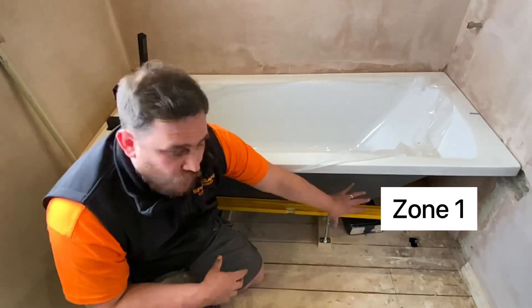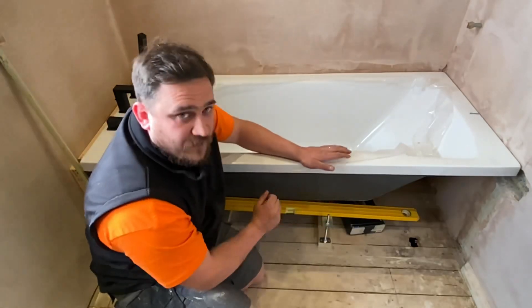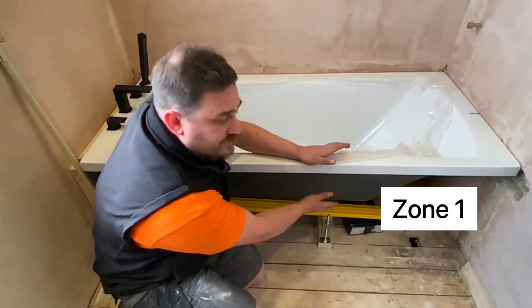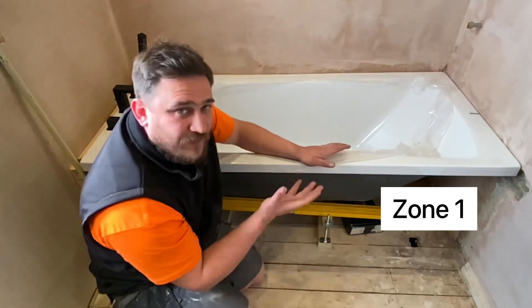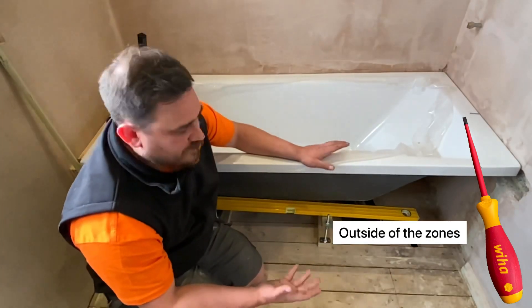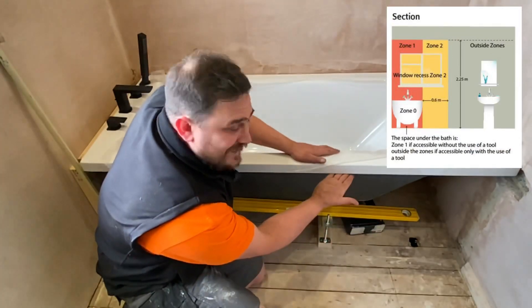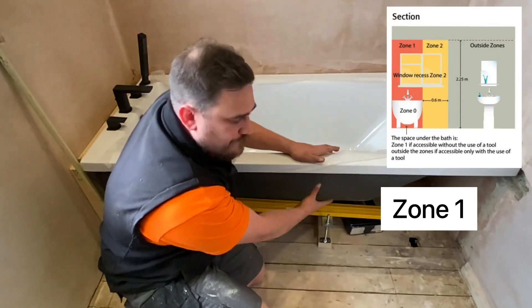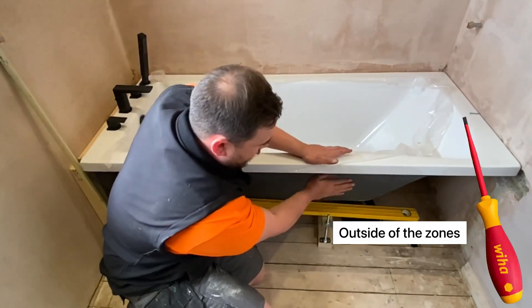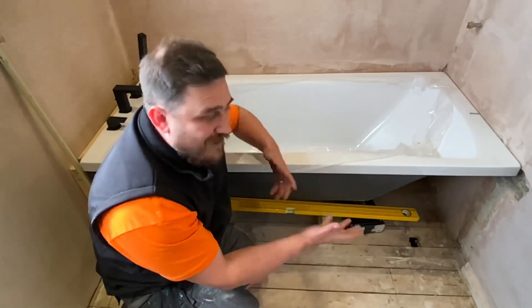As you can notice, there's no bath panel here, so at the minute this area under the bath would be classed as zone one. If we did put a bath panel here that was accessible without the use of a tool, it would still be classed as zone one. However, if it was a bath panel that required a tool to get into, we would then class this as outside of the zones - therefore we may be able to install whirlpool motors, etc.